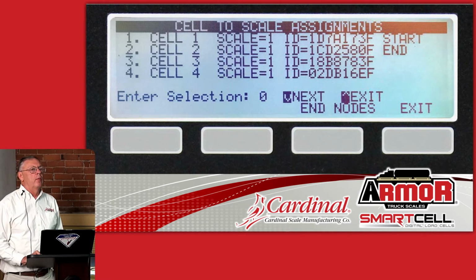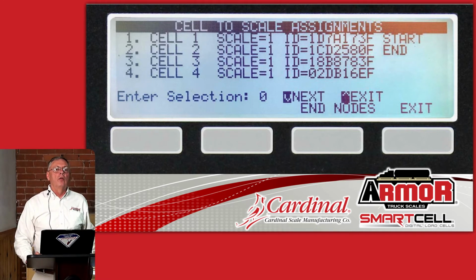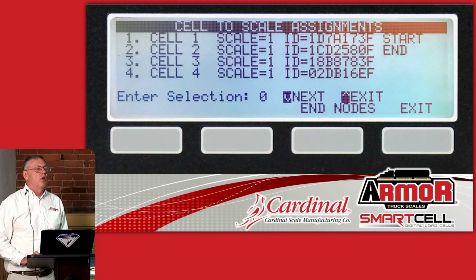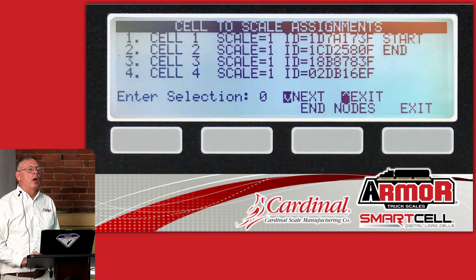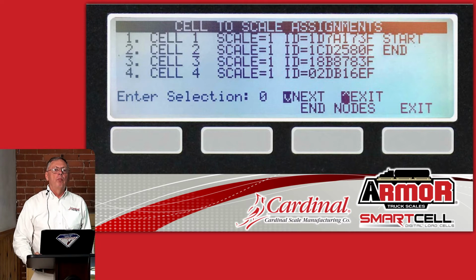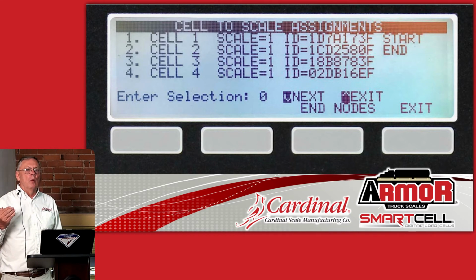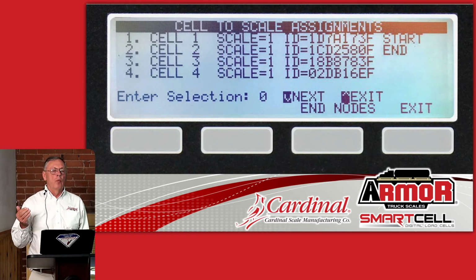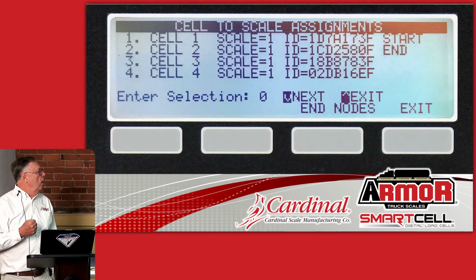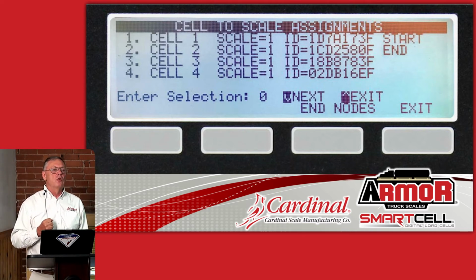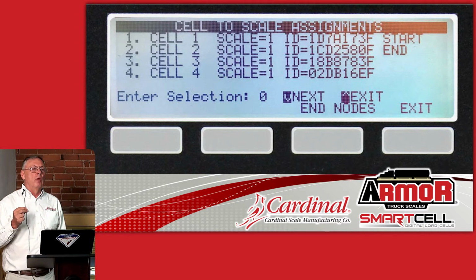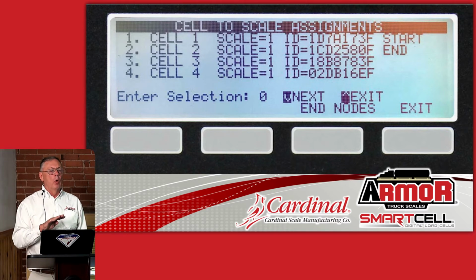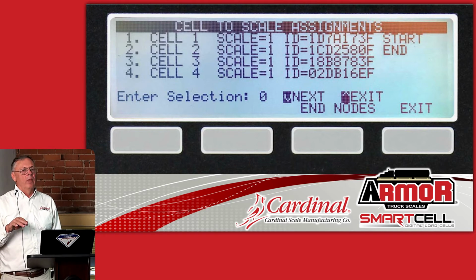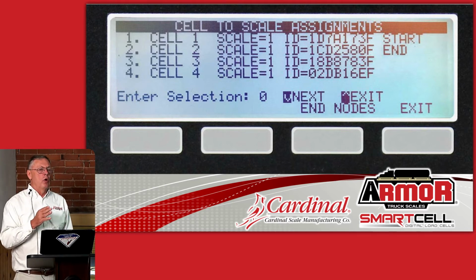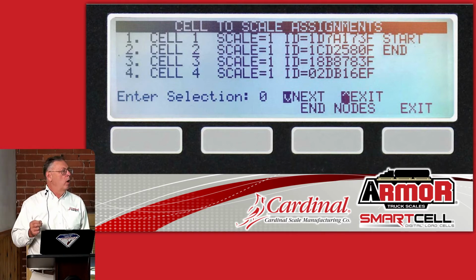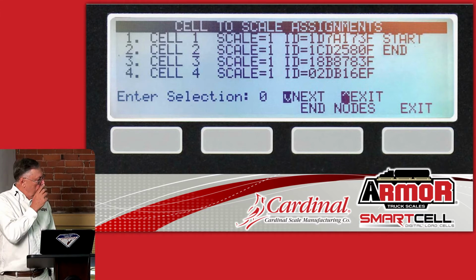When we're first setting up the scale here at the factory, we have to tell the system the serial number of each load cell, because basically we get a digital output from all the cells and we're going to total them up. Sometimes in multi-platform applications, we may have to tell the system that the first scale has got 4 load cells, the second one 4, the last one may have 8, and the system needs to know those serial numbers so it adds up those weights correctly. Now all of the IDs are put in here at the plant.